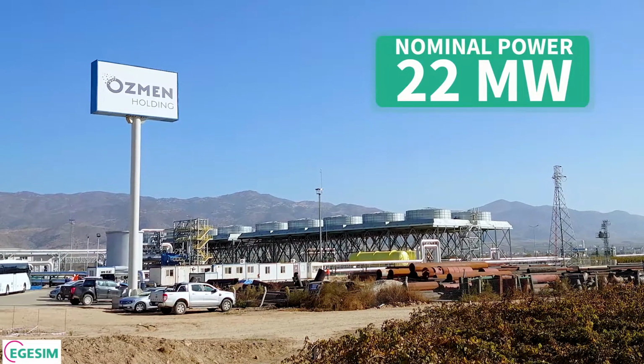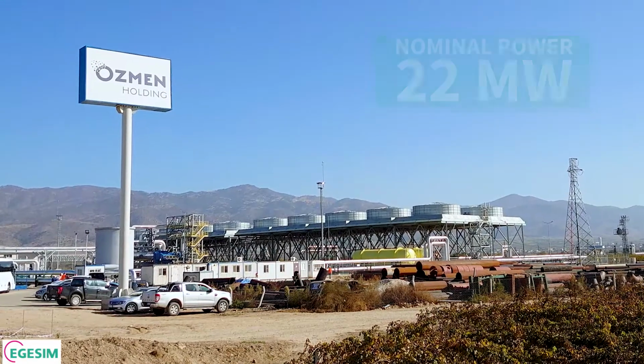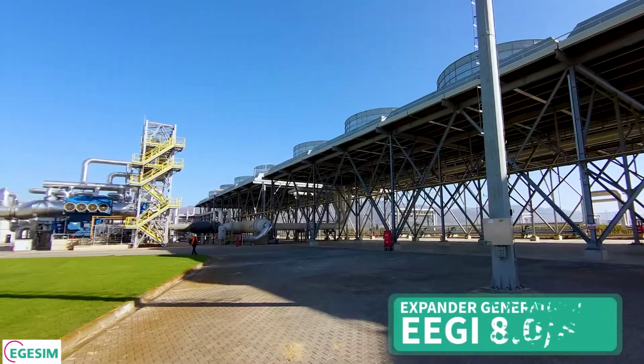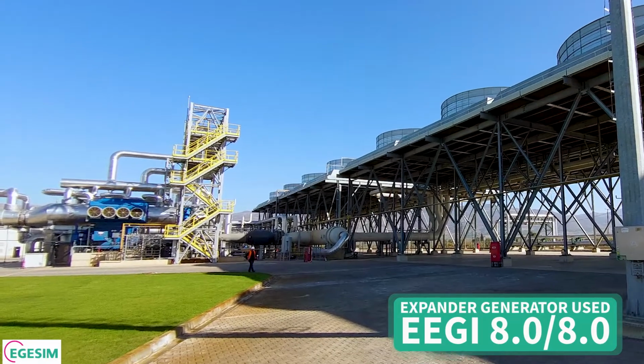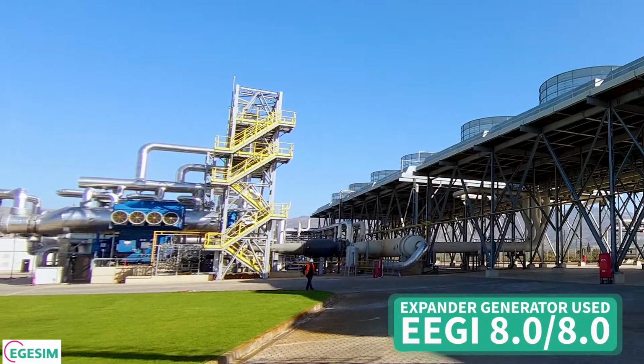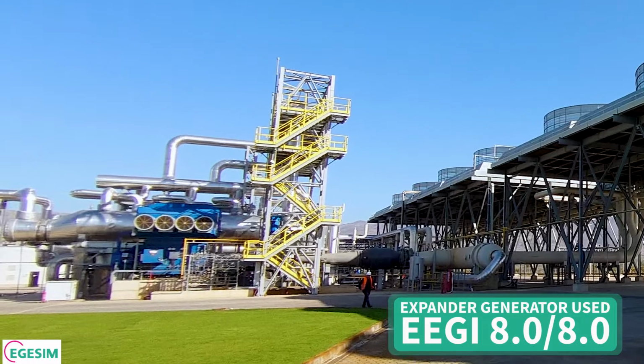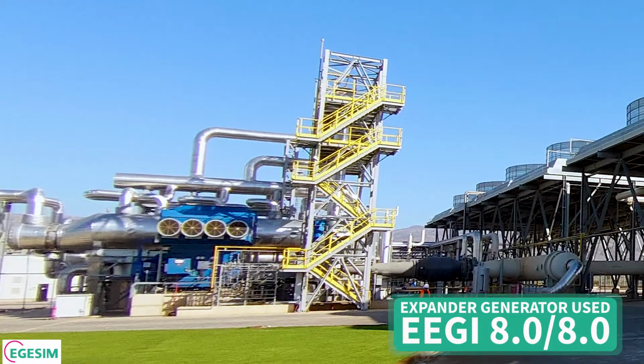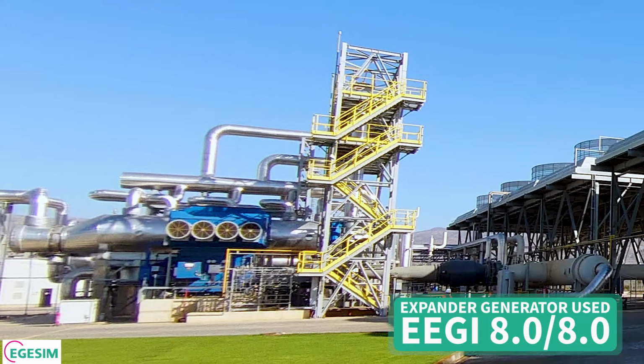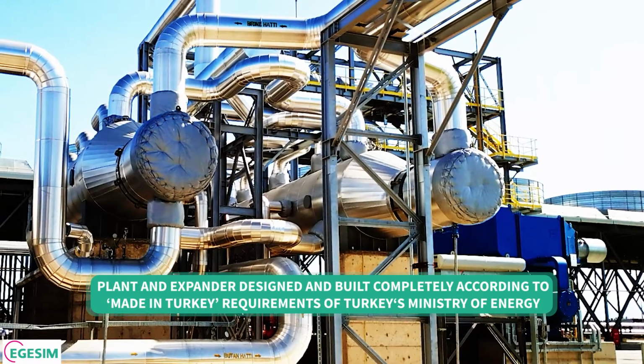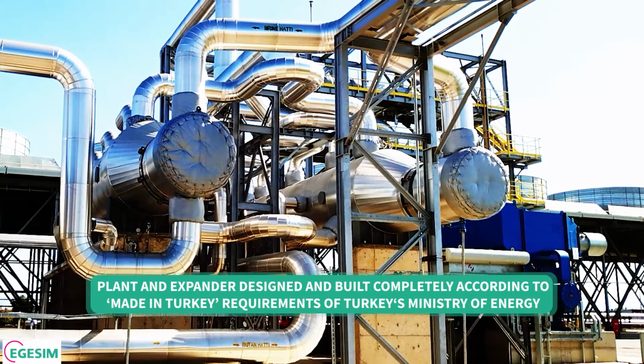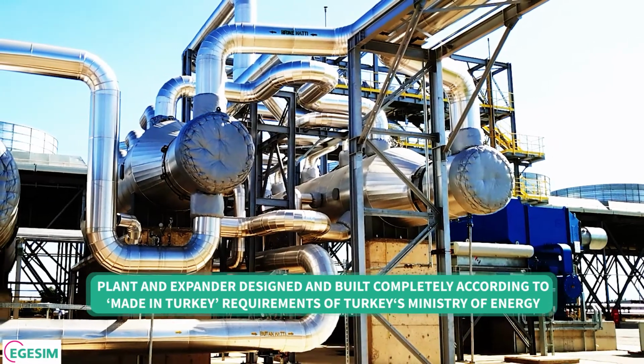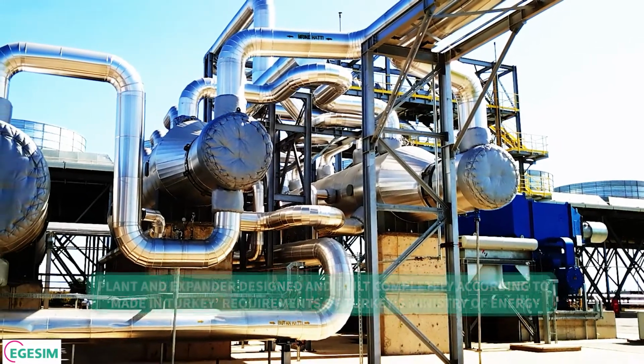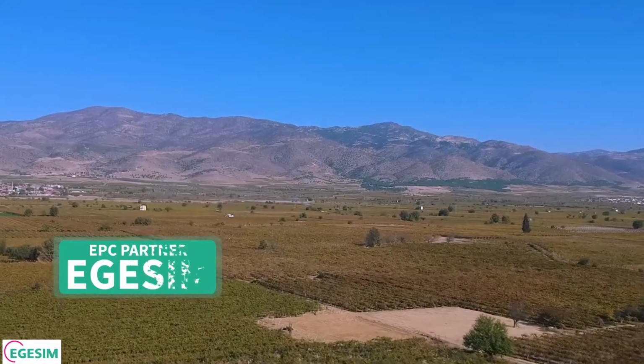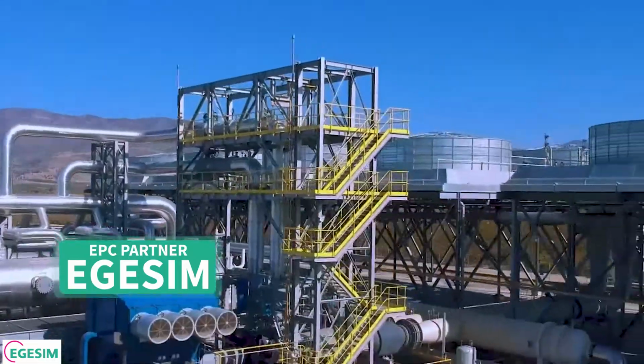This power plant is equipped with an Atlas Copco gas and process radial inflow turbine called EGI-88, which means dual stage, integrally geared and frame 8 impeller size. The whole power plant was made according to the design rules of the Made in Turkey requirements of the Turkish Ministry of Energy for a high feed-in tariff. It was completely designed, built and taken into operation by the Turkish EPC partner of ours, Egesim.